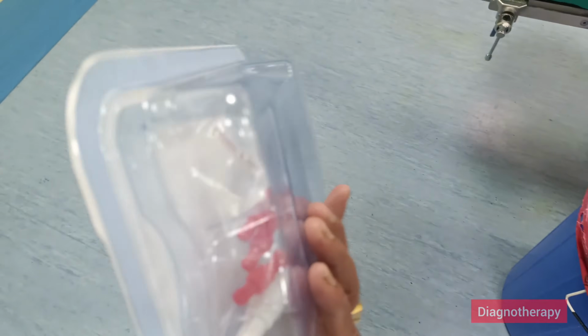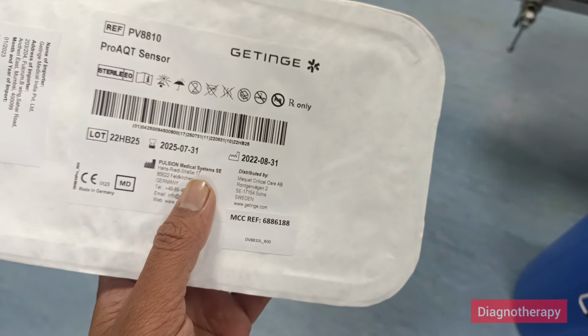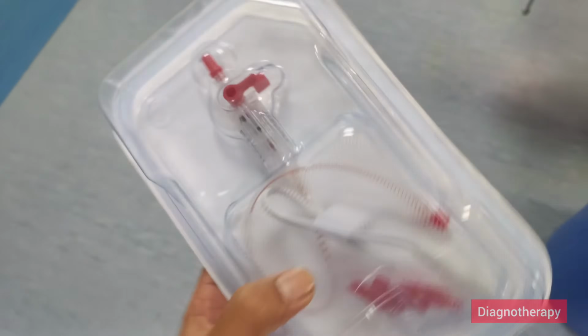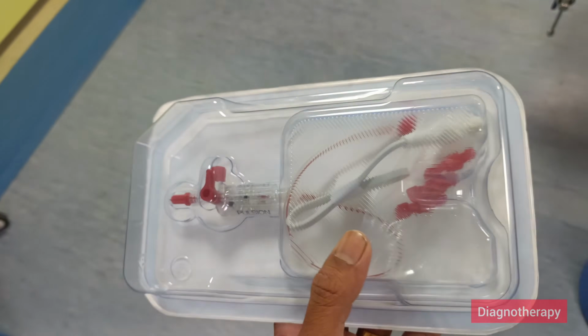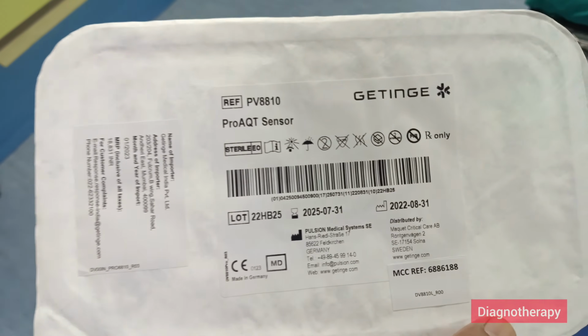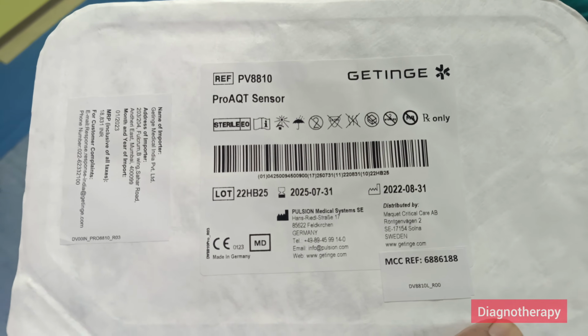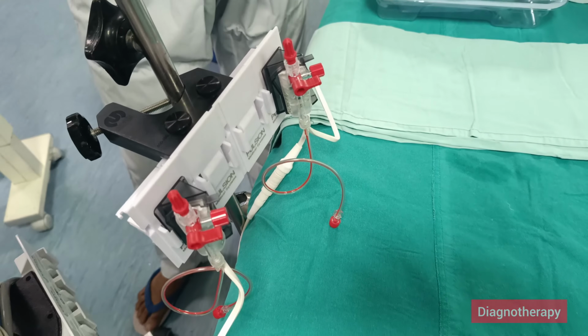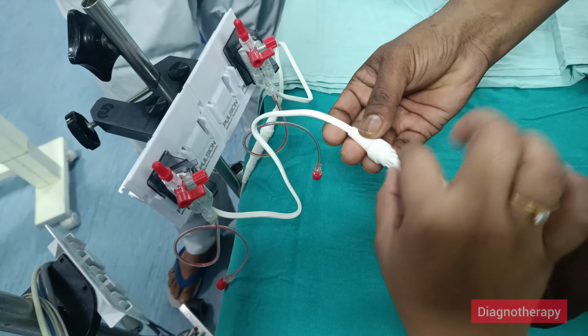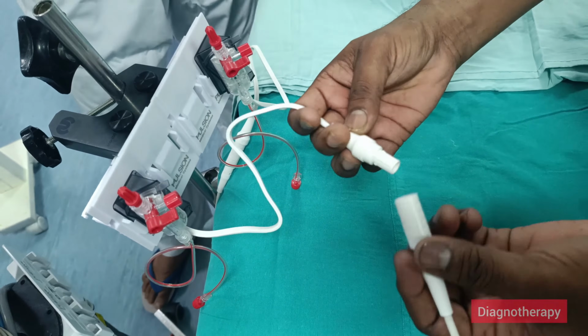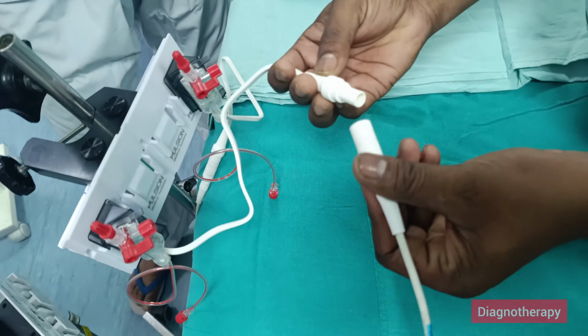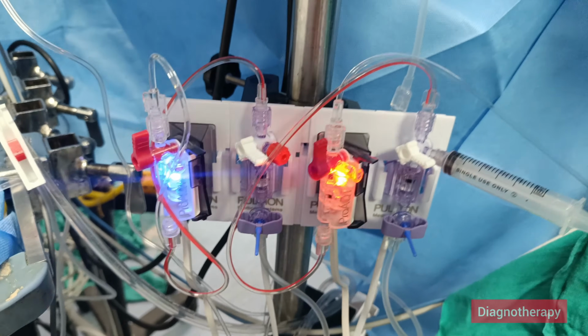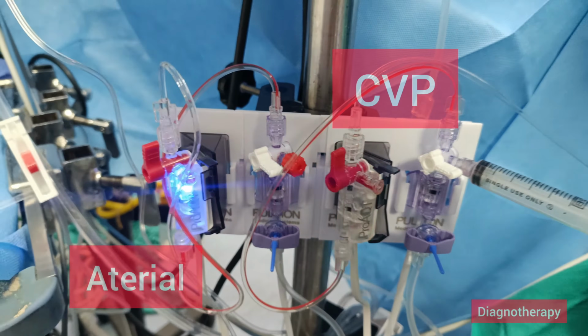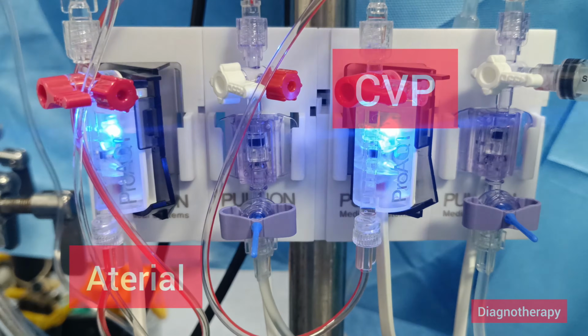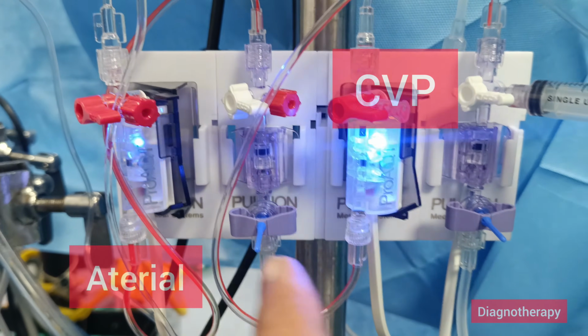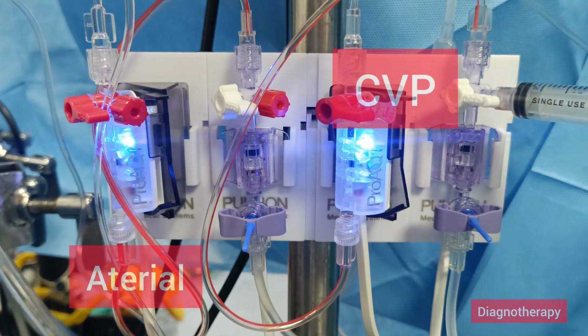This is the ProAQT sensor. So this type of two sensors will be used. In the packing, there is mention of the specifications and the data associated with this transducer. In the backside, you can see ProAQT sensor. This is how we attach the transducers, matching the notch, then pressing accordingly. So one we use for arterial and one for CVP. So depending on the use, we can shift the positions.